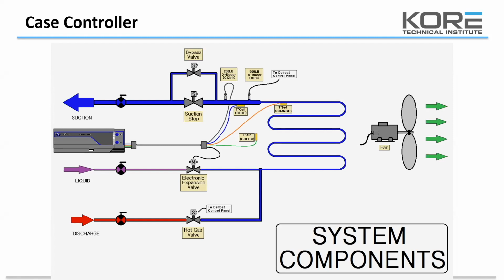So those blue ones are just going to go on the coils. Orange one in that hole. Right. The difference between the blue and the orange basically is that it's designed so they can easily go onto a pipe and be strapped on. Other than that, all of these temperature sensors are 10,000 ohm. So they're the exact same sensor. They just are a little bit different on the head for different applications. Cool.